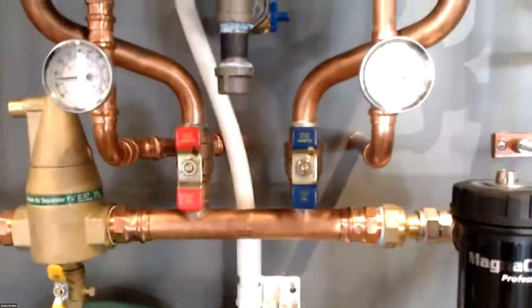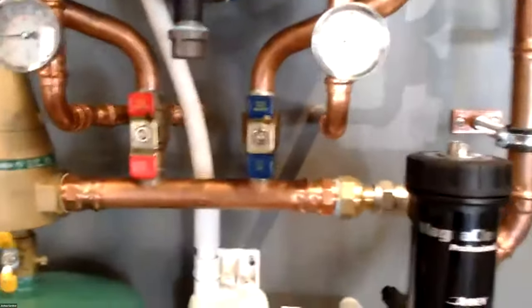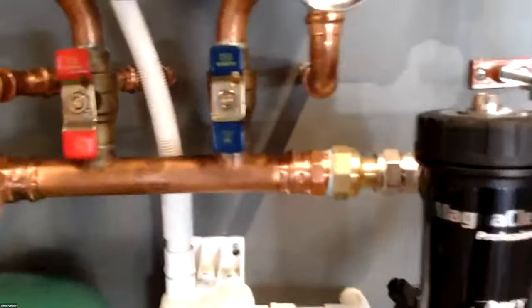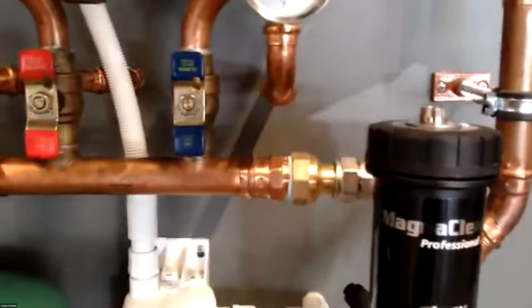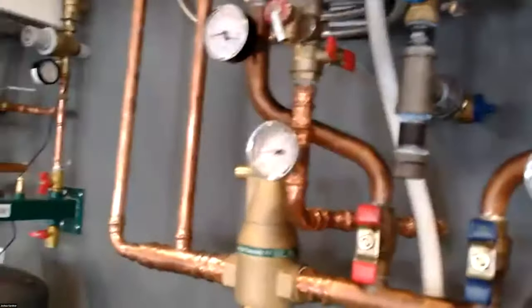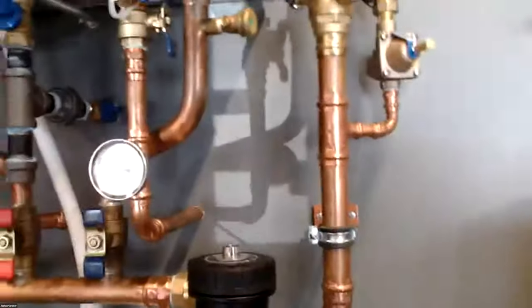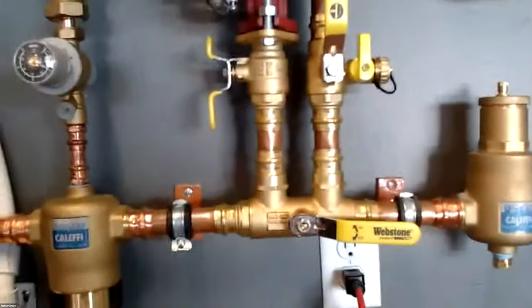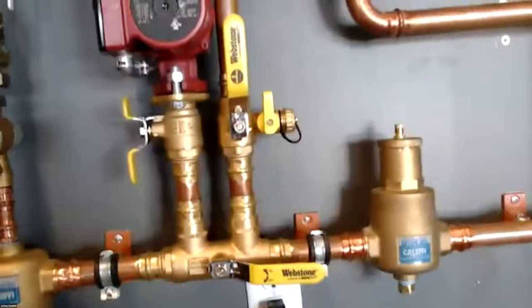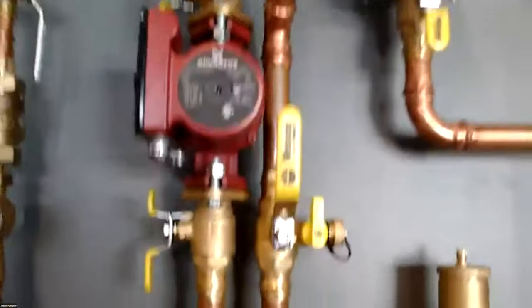But just note, if you are using closely spaced tees and you're using a header kit, you do need to leave some separation. You can't just install these items right up next to each other. You could have issues with hydraulic separation, and also it's going to make it hard to remove air from the system. The next one we have is a Webstone kit. I think a few manufacturers make this, but it's just a closely spaced T-kit.